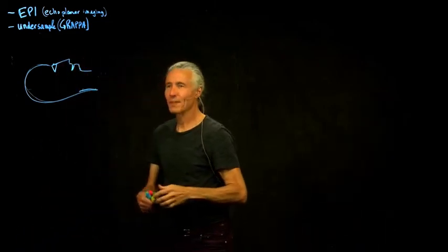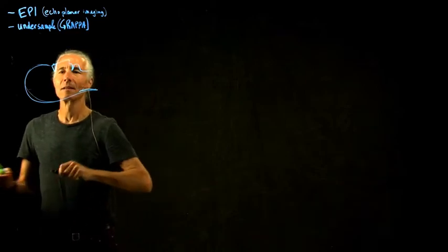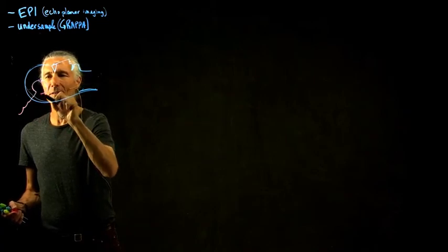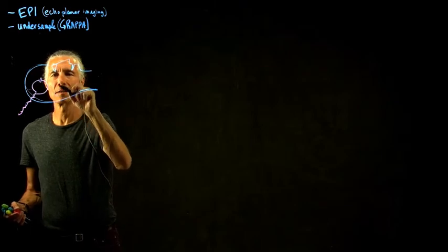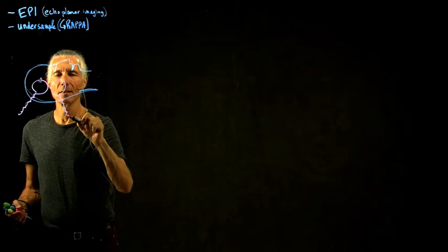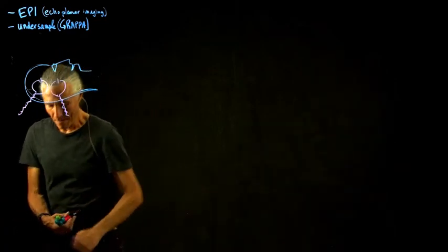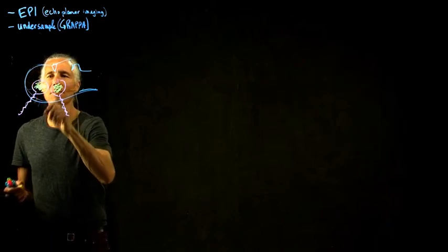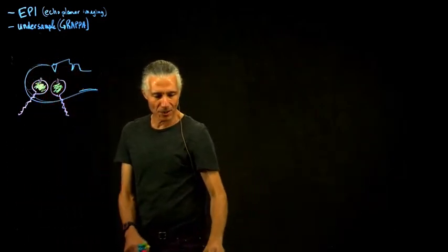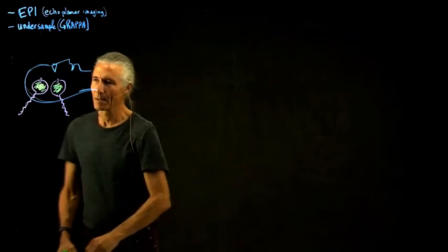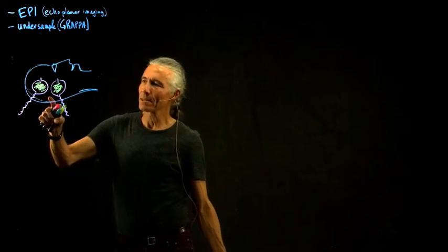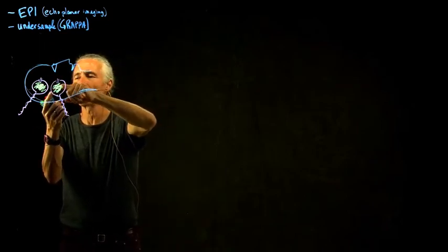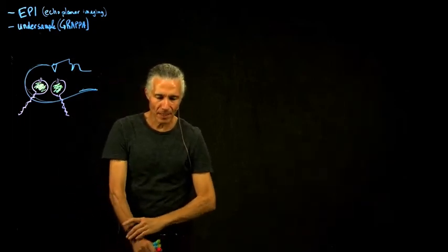So now if we put a coil like here, so here's the coil, there's the capacitor in the coil. That's one coil, and we've got another coil here. It's obvious that this coil is going to get a lot of signal from over here, and this coil is going to get a lot of signal from over here. So intuitively, you can see there's some additional spatial information coming from the coil, because it's not like a big coil that picks up uniformly from the head. It picks up more strongly from one part than another. And you can actually use that information.